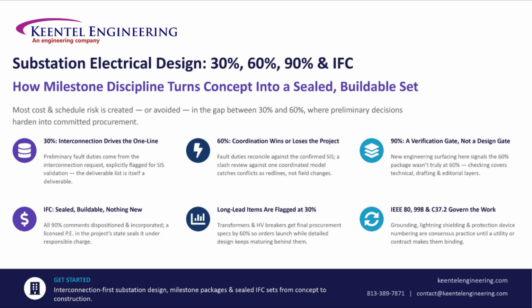Let's wrap up how a substation actually gets designed, package by package. Here's the truth most people miss. Most of the real cost and schedule risk gets created or avoided in the gap between 30 and 60%, right where preliminary decisions harden into committed procurement. At 30%, the one-line diagram is driven by the interconnection request itself, with preliminary fault duties explicitly flagged for validation once the system impact study comes back.